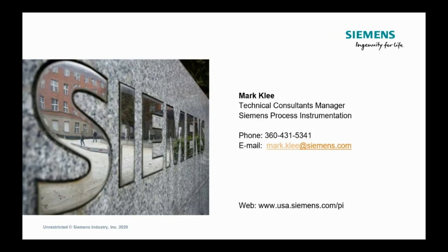These next two are about Class 1 Div 1. Is it a seal off only, or conduit attached to it? That of course is really going to be a matter of the National Electric Code as to what the requirements are between your classified and unclassified environment. Probably want to talk about the particulars of that one offline. I'd say reach out to Ponton and let's look at that specific, especially when we're dealing with explosion proof. Generic answers can sometimes get you into a little bit of trouble, and we want to be sure we're understanding enough about the process that we don't give a wrong answer there. But generally speaking, there's going to be a seal off based on NEC regulations as far as how you separate between the two environments.